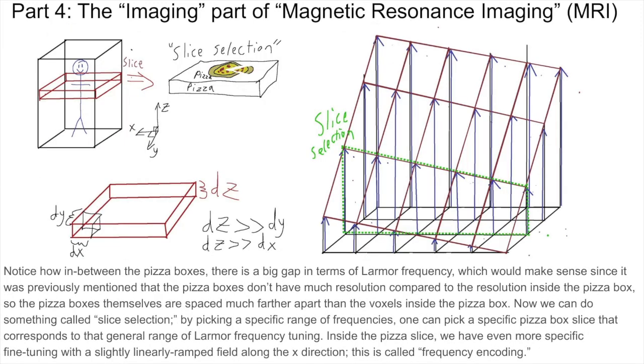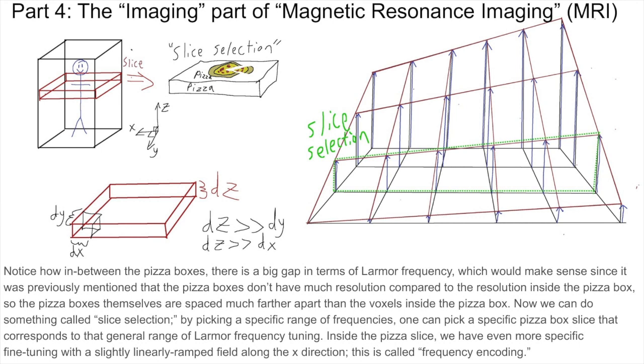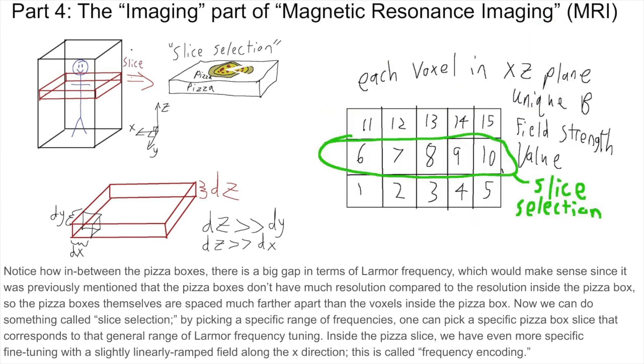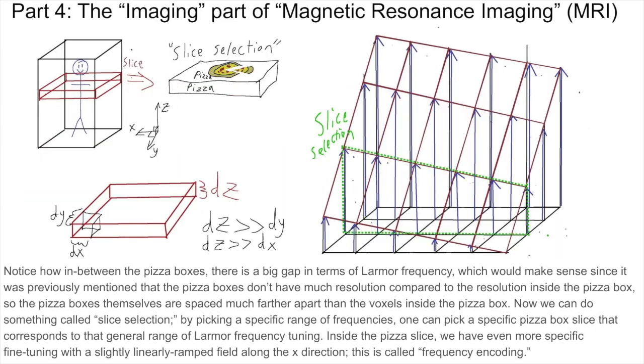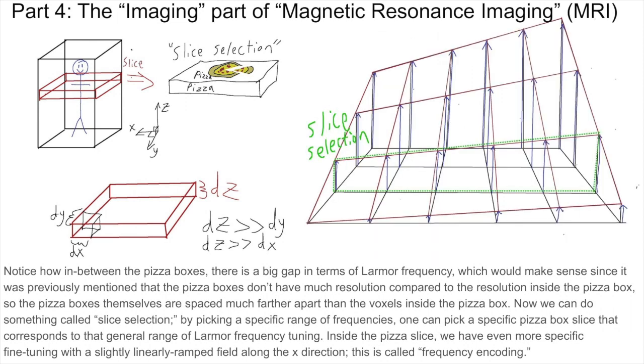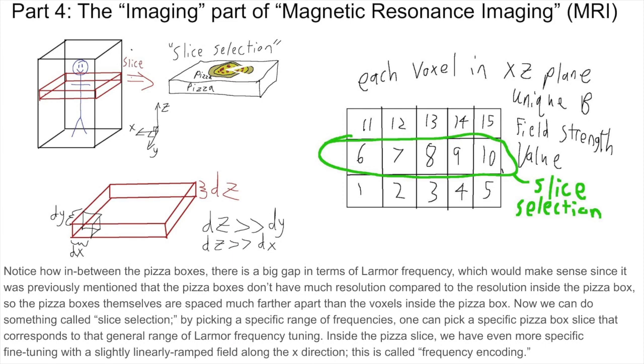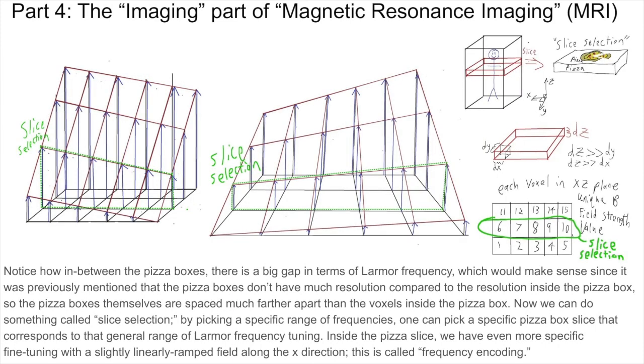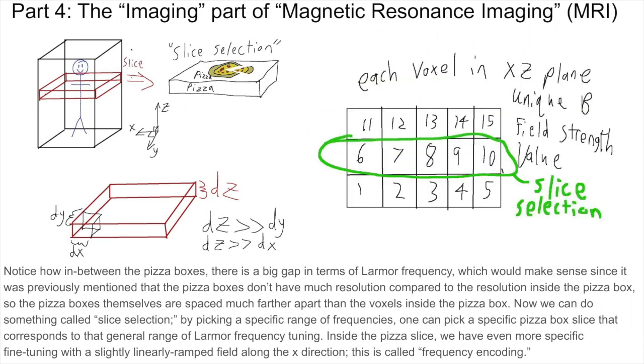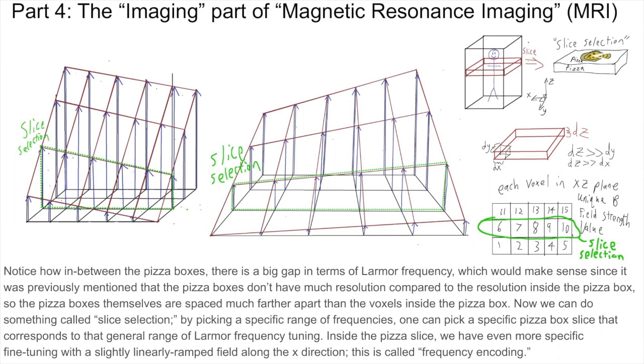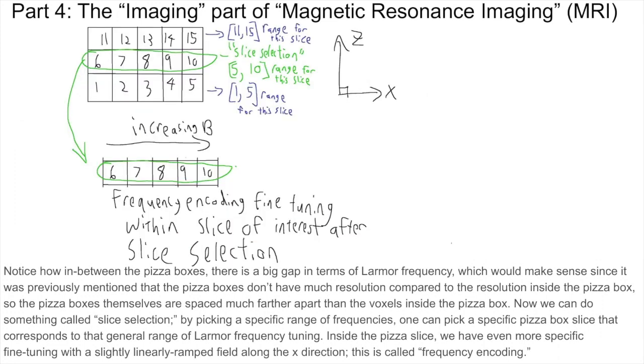Notice how in between the pizza boxes there is a big gap in terms of Larmor frequency, which would make sense since between the pizza boxes there is much less resolution compared to the resolution inside within a pizza box. So the pizza boxes themselves are spaced much farther apart than the voxels within inside the pizza box. Now we can do something called slice selection. By picking a specific range of frequencies, one can pick a specific pizza box slice that corresponds to that general range of Larmor frequency tuning. Inside the pizza slice, we have even more specific fine-grained fine-tuning with a slightly linearly ramped field along the X direction. This is called frequency encoding.